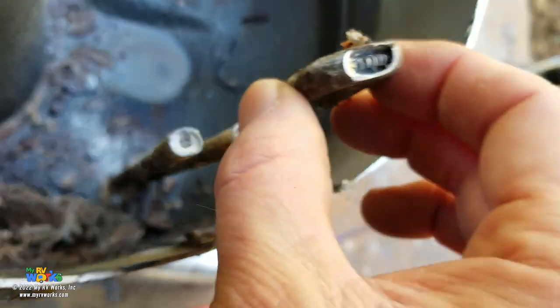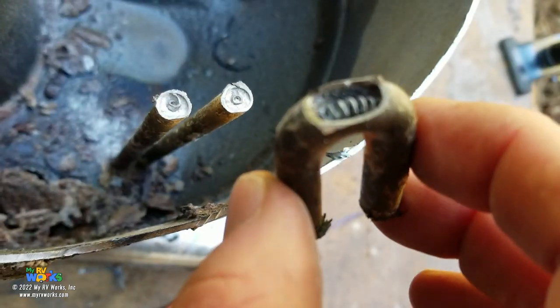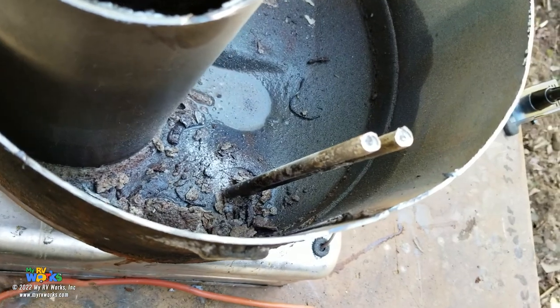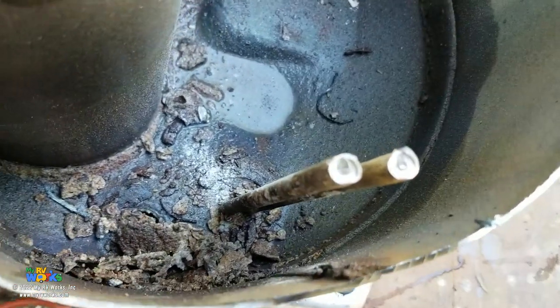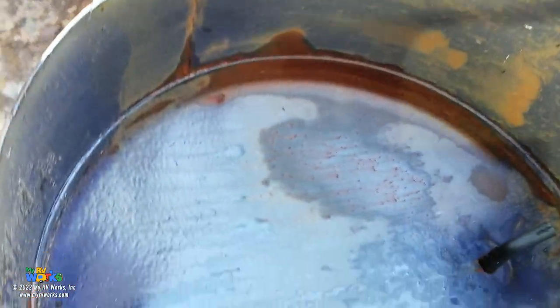And so I basically cut it in half and then snipped off the top of it to show the inside of the heating element. So when you're reading your ohms resistance, that should be about 10 ohms, you're reading that wire, the spring wire. Okay, so what do we have next door here? So I went ahead and took the time to cut this one open.